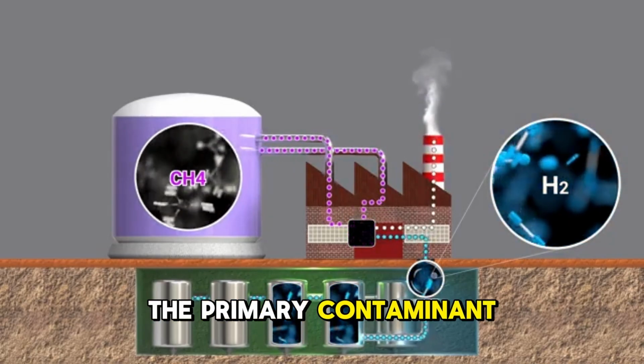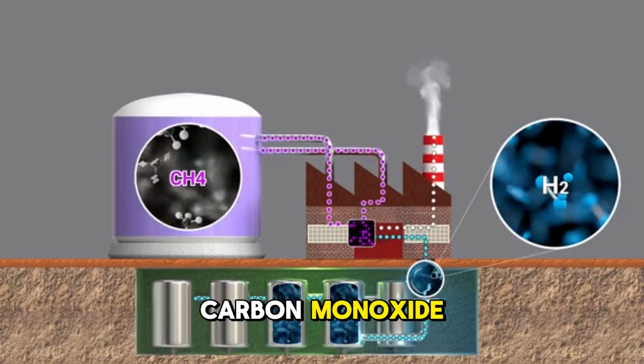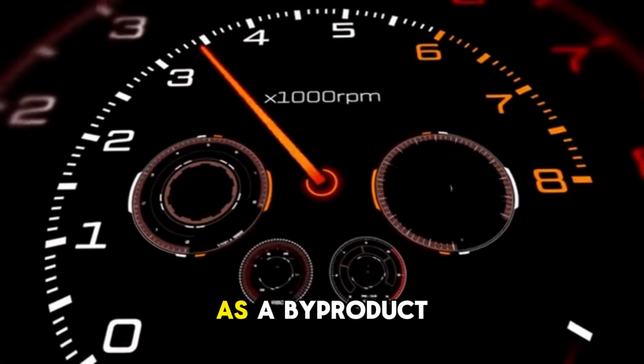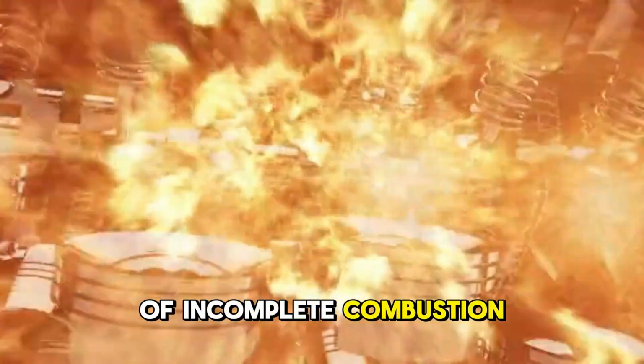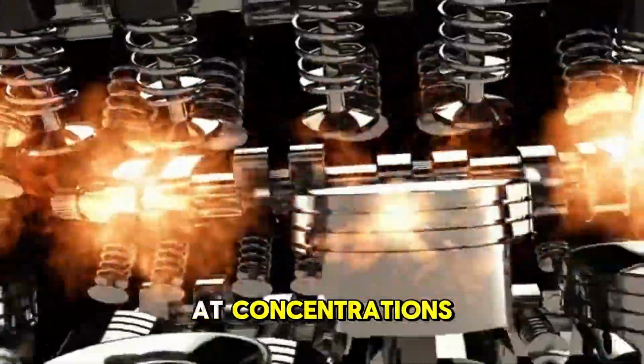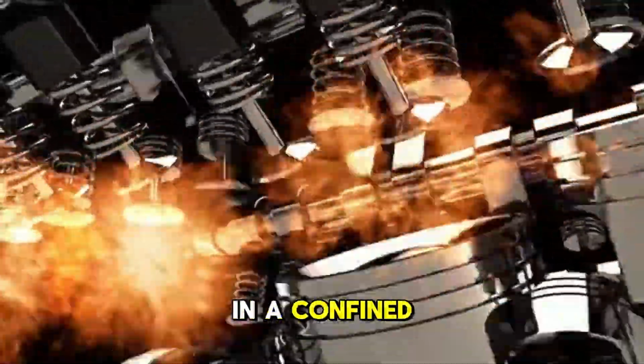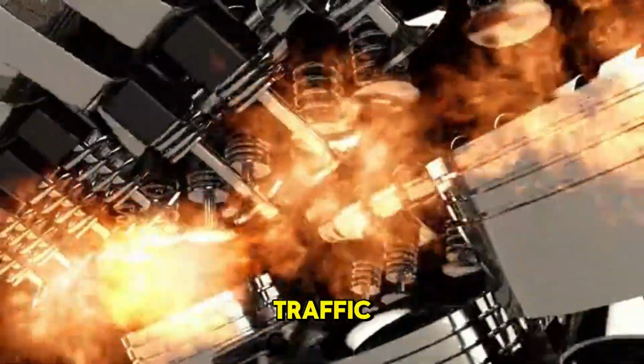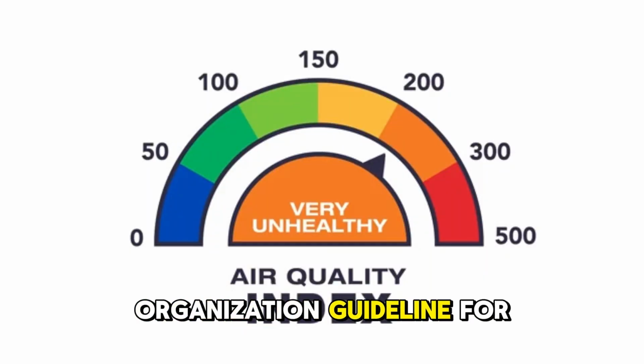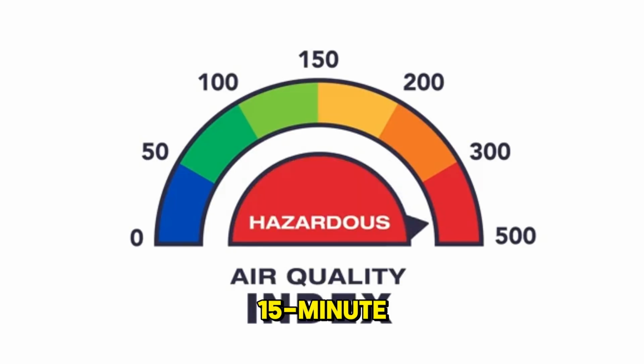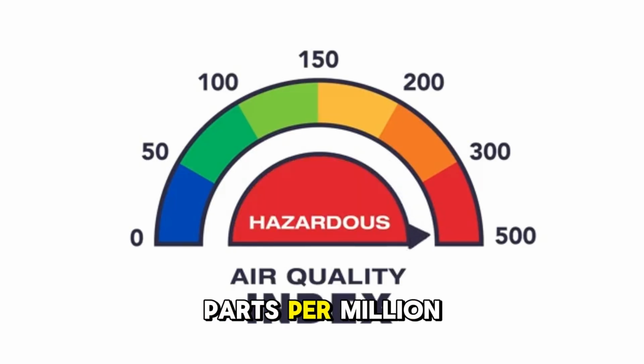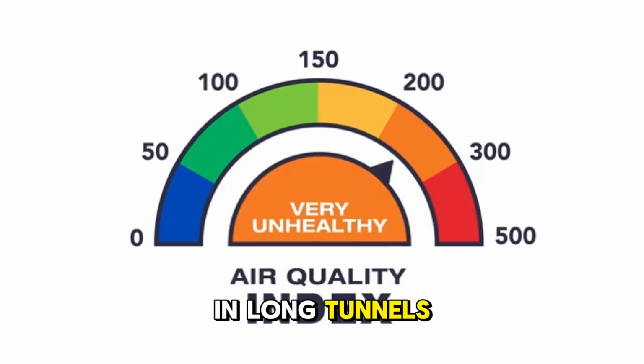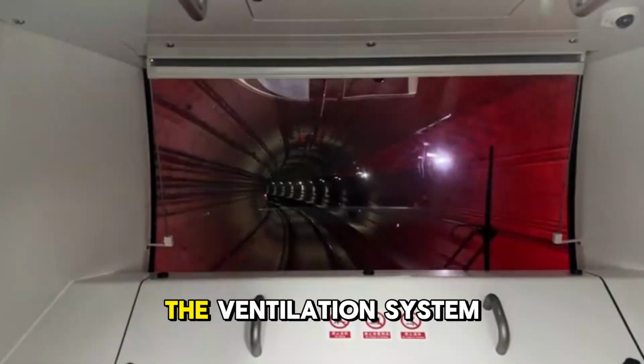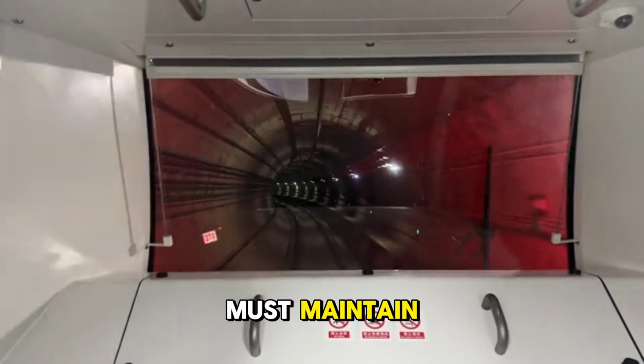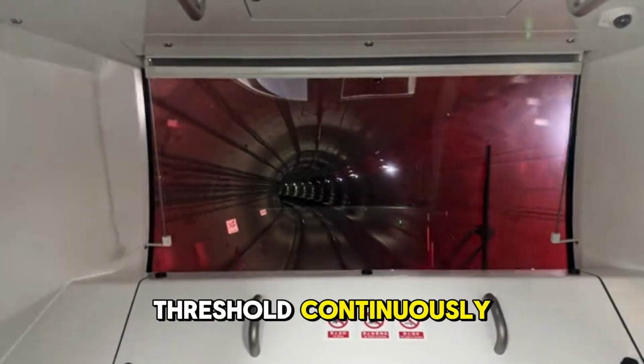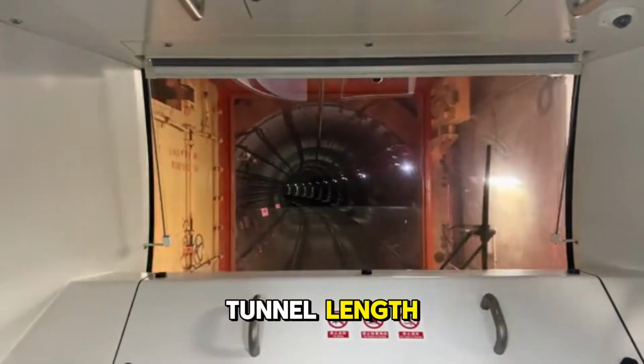The primary contaminant of concern is carbon monoxide. Vehicle engines produce CO as a byproduct of incomplete combustion. CO is toxic at concentrations reached relatively quickly in a confined space with heavy traffic. The World Health Organization guideline for CO exposure over a 15-minute period is 100 parts per million. In long tunnels, CO could exceed this in minutes.